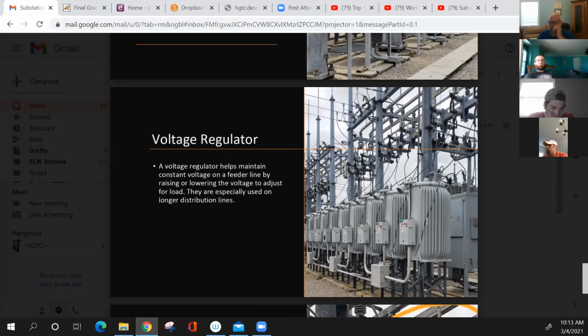Professor Shoemaker says that Santee Cooper does some of their phasing out in the field to tell which phase it is to raise and lower a voltage regulator. And you could put a primary voltage indicator out there, and it would tell you which phase, because you could actually see the voltage raising and lowering out in the field. And it says in the description, voltage regulator helps maintain constant voltage on a feeder line by raising or lowering the voltage to adjust for load. They are especially used on longer distribution lines. And being that he put that in their longer distribution lines, you will see these out in the field.